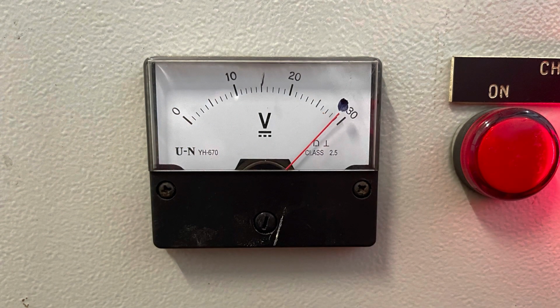Okay, after testing the genset, recording the analog voltmeter and witnessing the voltage drop in slow motion, you can see the characteristics of different types of battery during startup. For stronger batteries, the voltage drop won't go below 20 volt DC; it will stay above 20 volt DC. However, as your battery gets older, the voltage will drop slightly below 20 volt. But my advice is always to allow the battery voltage to stay above 15 volt DC during the cranking time.